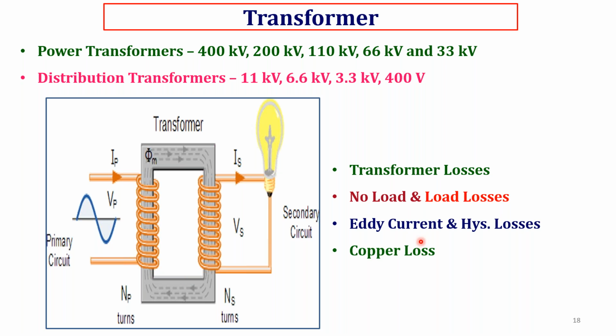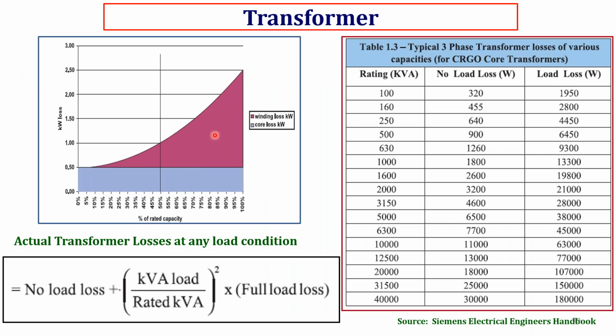As we know, among the basic things of the transformer, the loading percentage of the transformer is very important. Often you have to load the transformer at 50%, which is economical for the transformer losses. And you can see this graph from the transformer manufacturers themselves, or you can download it from the respective website to get the loading percentage losses incurred in the transformer, and the right side will give the individual losses for the different capacity ratings available in the series.